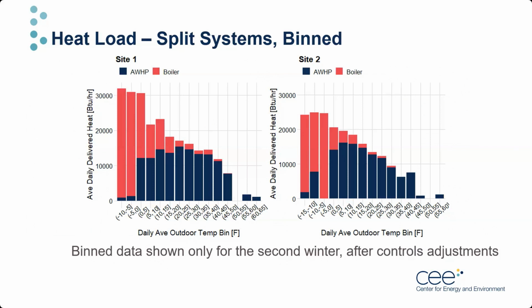Moving from right to left on each plot, we can see more clearly that the boiler begins to seamlessly make up for the shortcomings of the air-to-water heat pump as it starts to lose capacity in cold winter. Another point to note is that the Bosch compressors at these sites are rated to -4 degrees, which is why you'll start to see a drop-off at that point. Next slide.